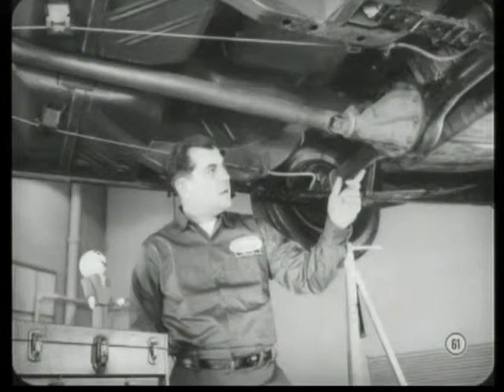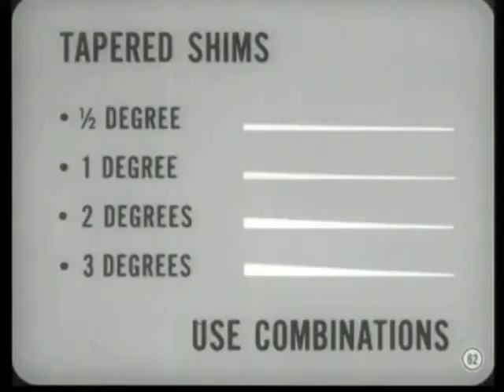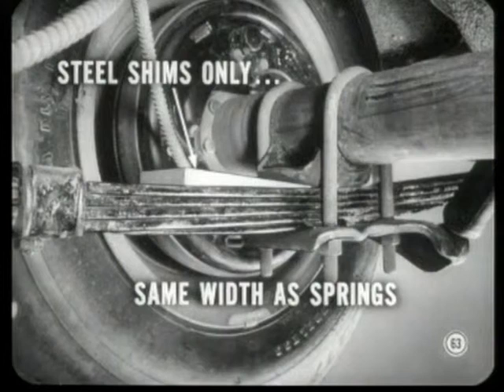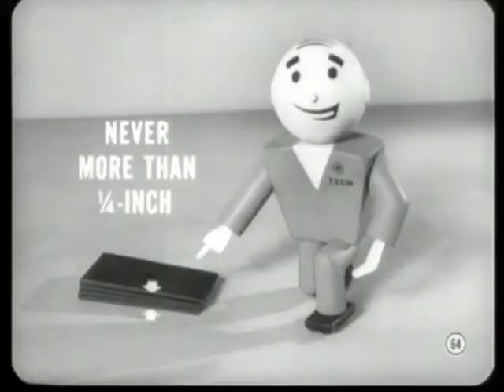That depends on which one you use, Frank. There are 4 different sizes, with angles of a 1/2 degree, 1 degree, 2 degrees, and 3 degrees. You can use combinations to get within a 1/2 degree of the perfect setting. Don't ever use anything other than a steel shim. And be sure it's the same width as the springs. There's another important caution here, too. Don't ever use a shim pack that's over a 1/4 inch thick at the center. If you need that much, there's something else wrong, such as a mislocated spring seat.